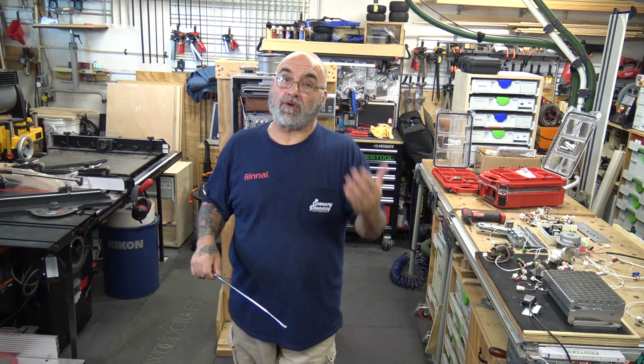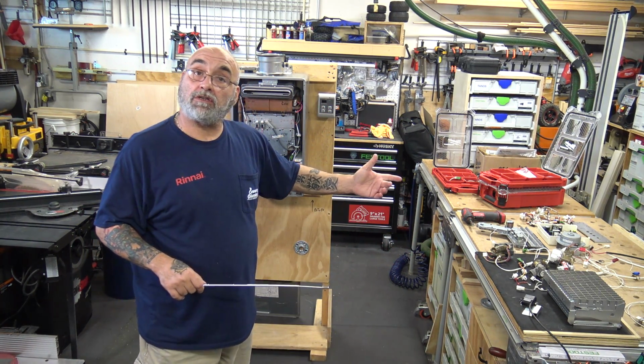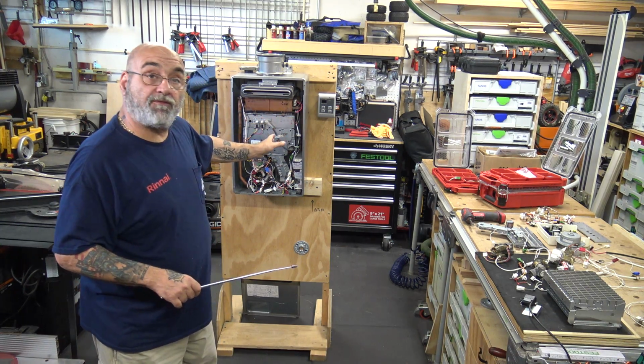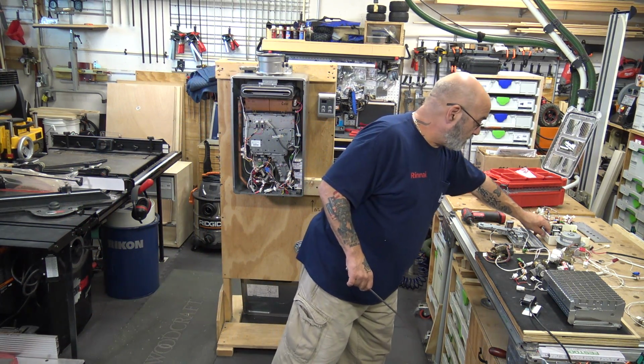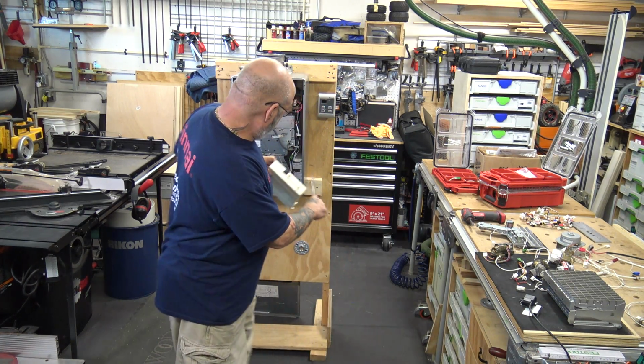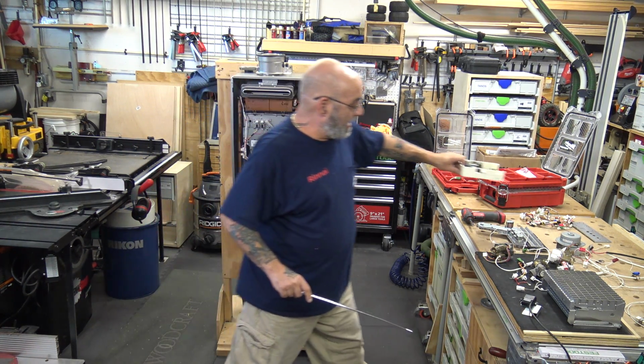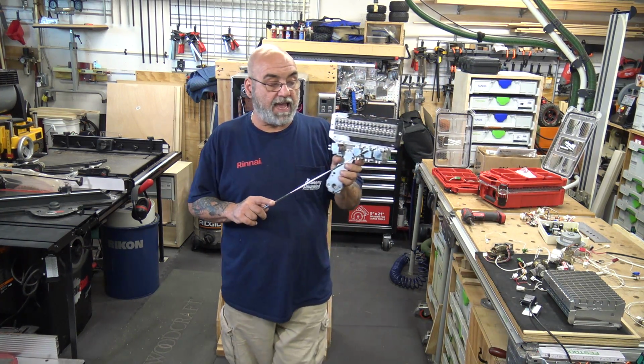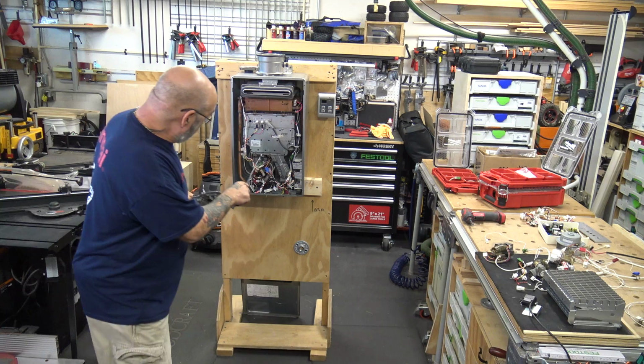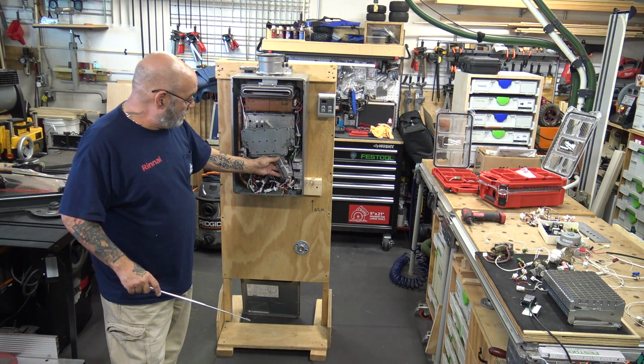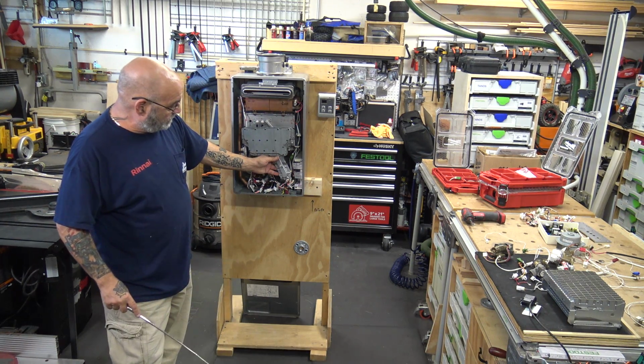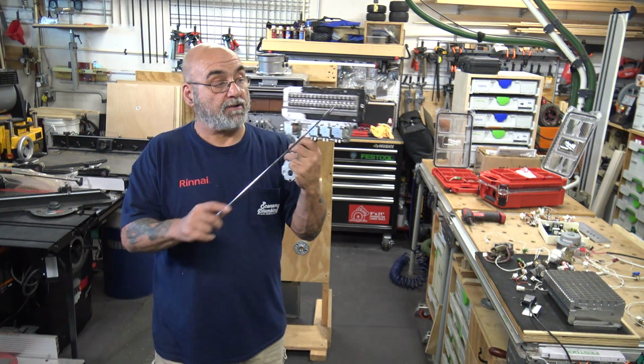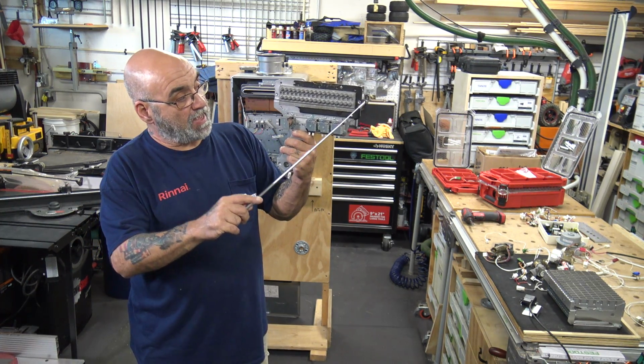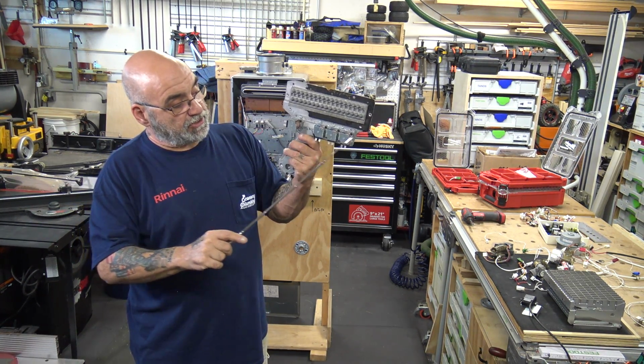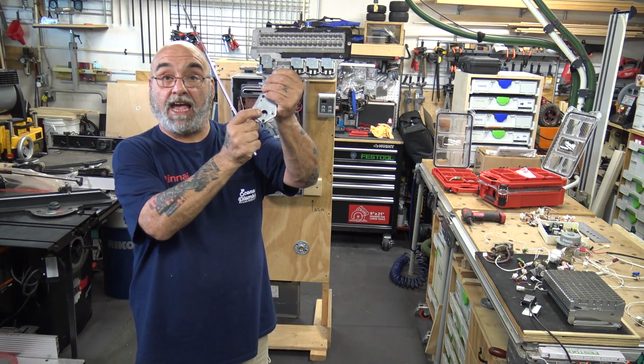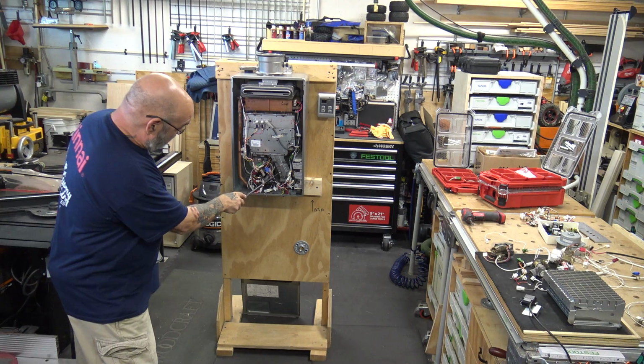So as you increase the flow of water, the faster the water turbine spins, the more it will ramp up the burner through the PC board right here, and will open up the gas solenoids, which are right here, which would then open up and allow gas to enter the actual burner. There is your burner, there are your orifices. You got your gasket that seals it. This is on the back side. This is what's mated to your gas valve, right here. Here's your gas valve. It's mated to your gas valve.